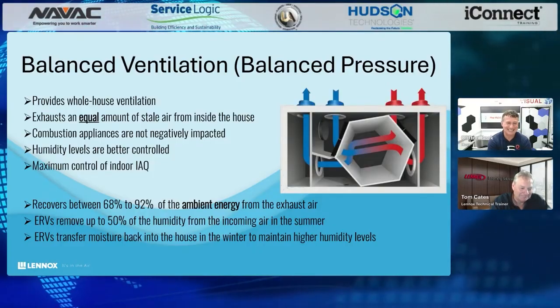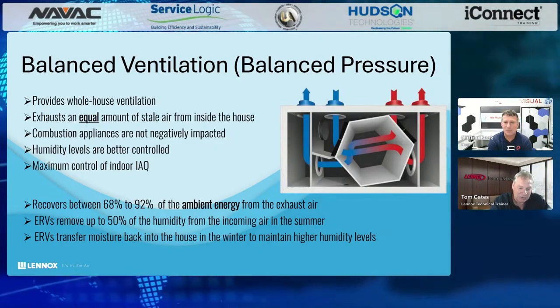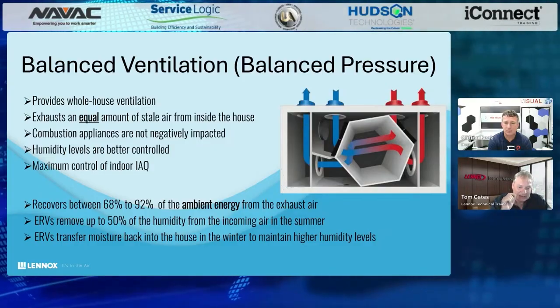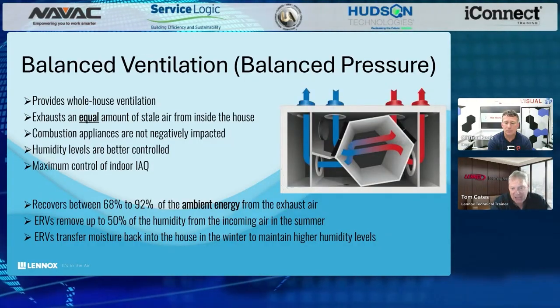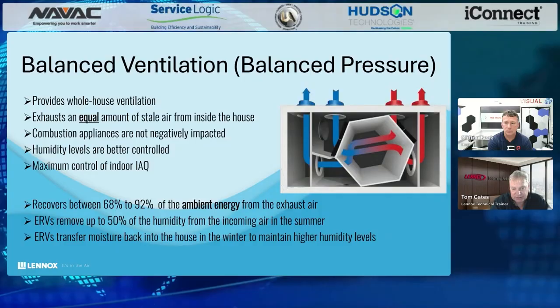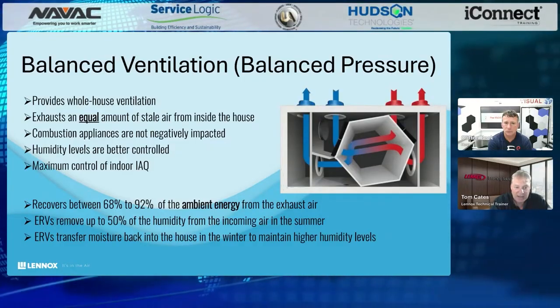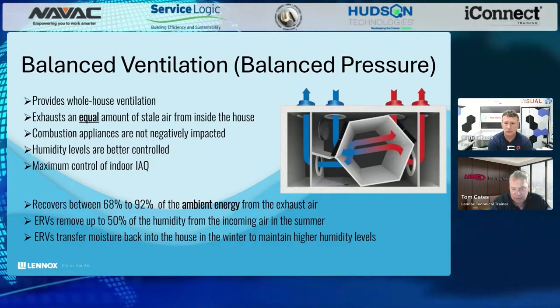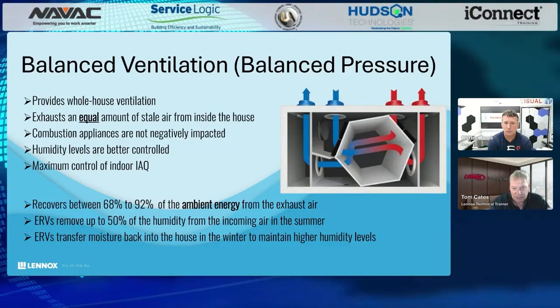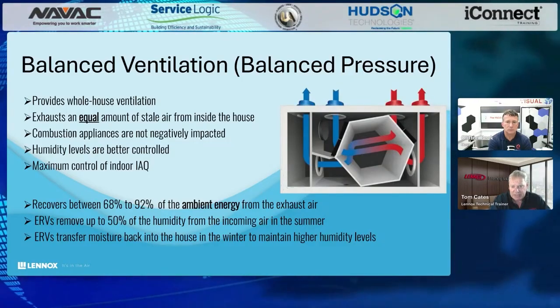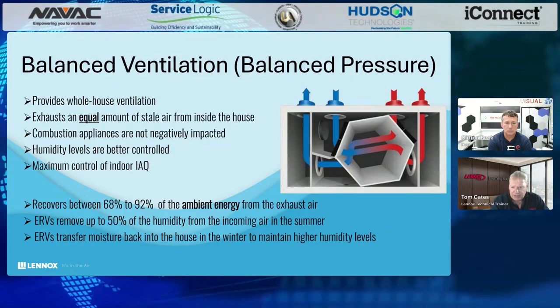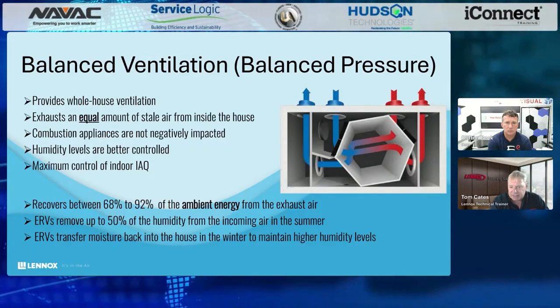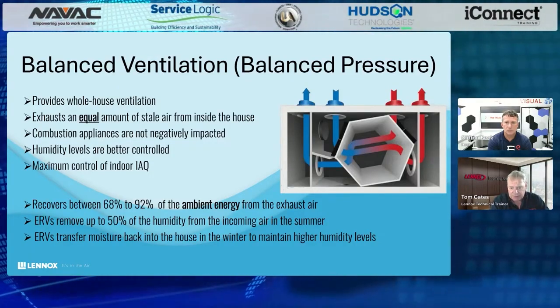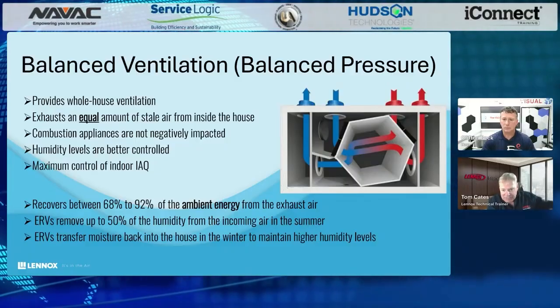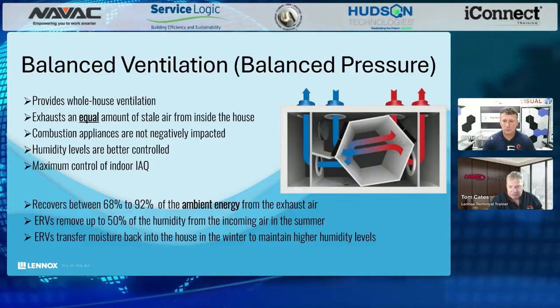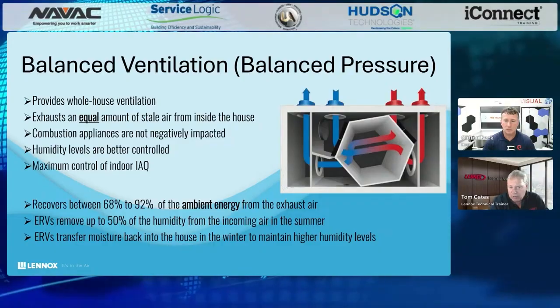But it's important that we understand that the energy transfer that happens in these devices is essentially 100% free. And what happens on the exhaust side has no influence or bearing on what happens on the supply side, which is really nice. I think about furnaces, the intake and the exhaust of a high efficiency furnace. Typically, they have to be on the same side of the building for pressure so that you don't trip your pressure switch and things of that nature. We don't have that same problem with this.